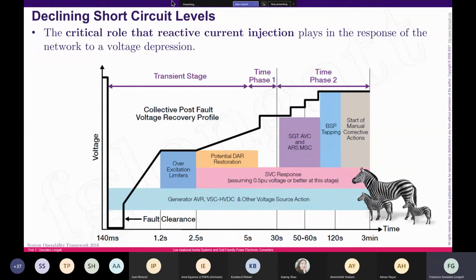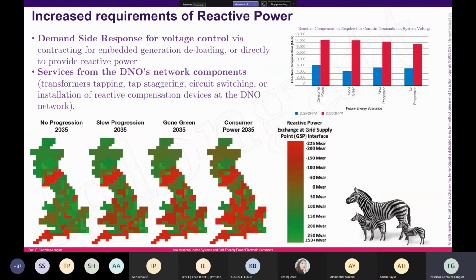Let's move forward. What about reactive power injection? It's very simple: if we reduce the number of synchronous generators, the traditional synchronous generator has the possibility of delivering or absorbing reactive power. That's extremely basic in the case of a synchronous machine, where we can modify the field winding current and overexcite or underexcite the generator to change the reactive power production or consumption.